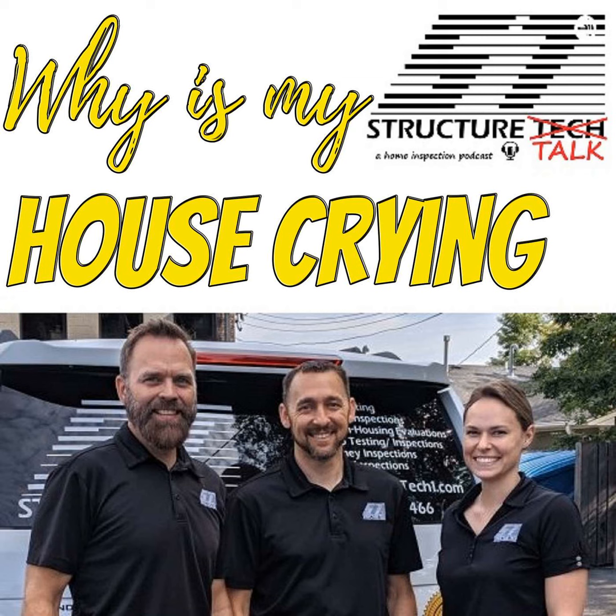I've got a good video - I did a blog on this years ago where the house was under so much pressure that when I got the door close to being closed and let it go, it just closed all by itself. It wasn't that the door was out of alignment; there was such an imbalance in the supply and return ductwork that the basement was sucking a ton of air. It's a fun little do-it-yourself test.